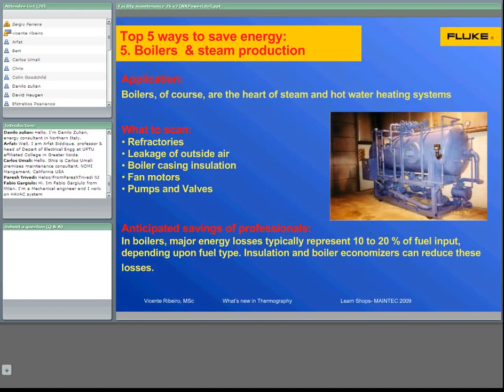These small steam traps, maybe placed 5 meters away, I can check with the camera, from a distance. Traditionally this is done three or four times a year, with acoustic methods. But look at this trap here. It's a trap that has a cost. It's a trap in a school. A trap that has a cost of about 100 euro. Now it's 85 pounds, but it's about 100 euro.